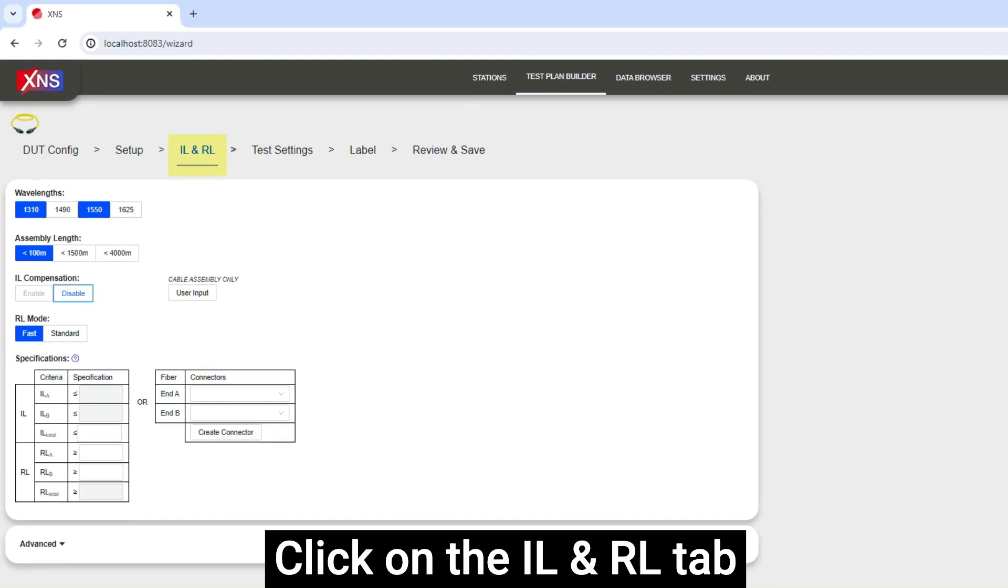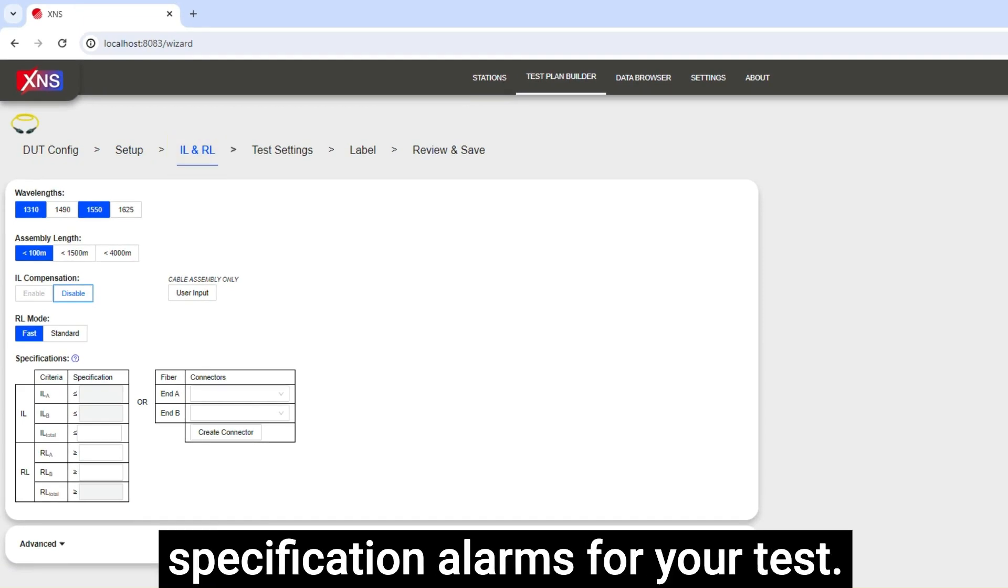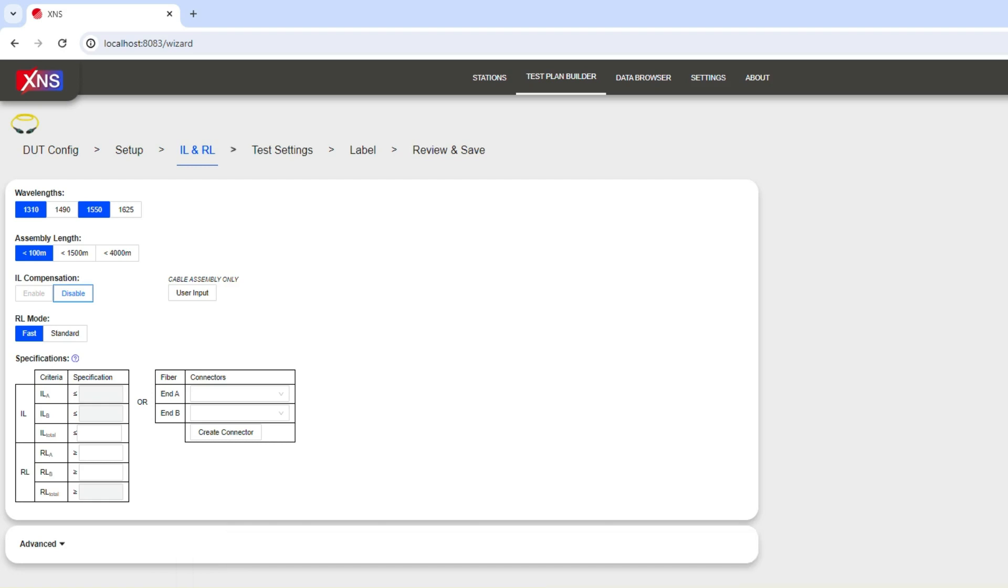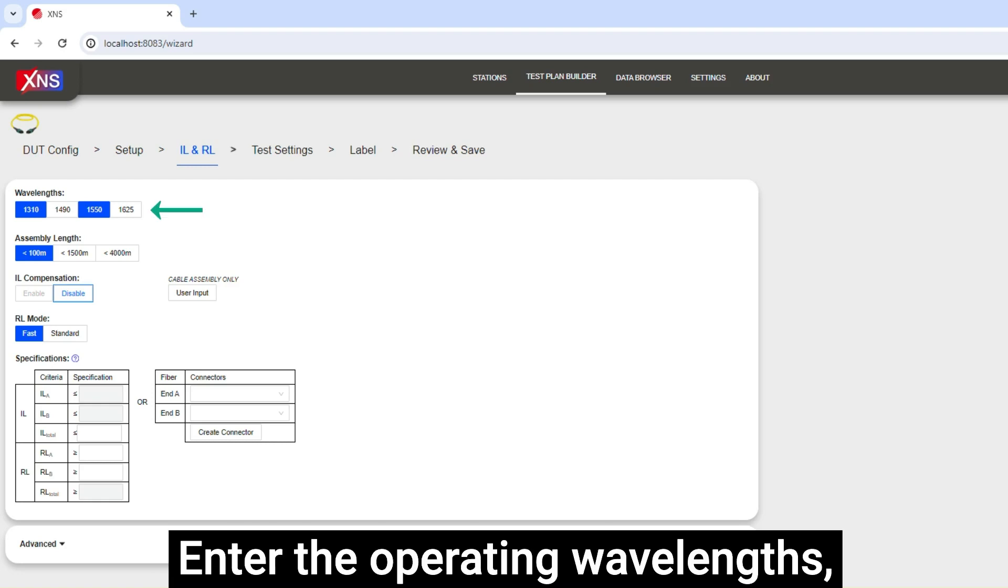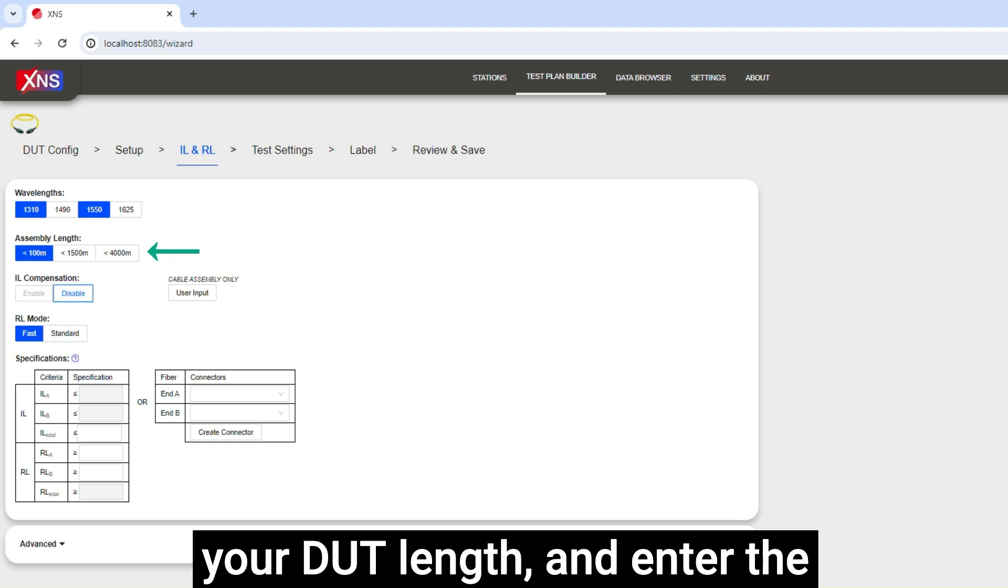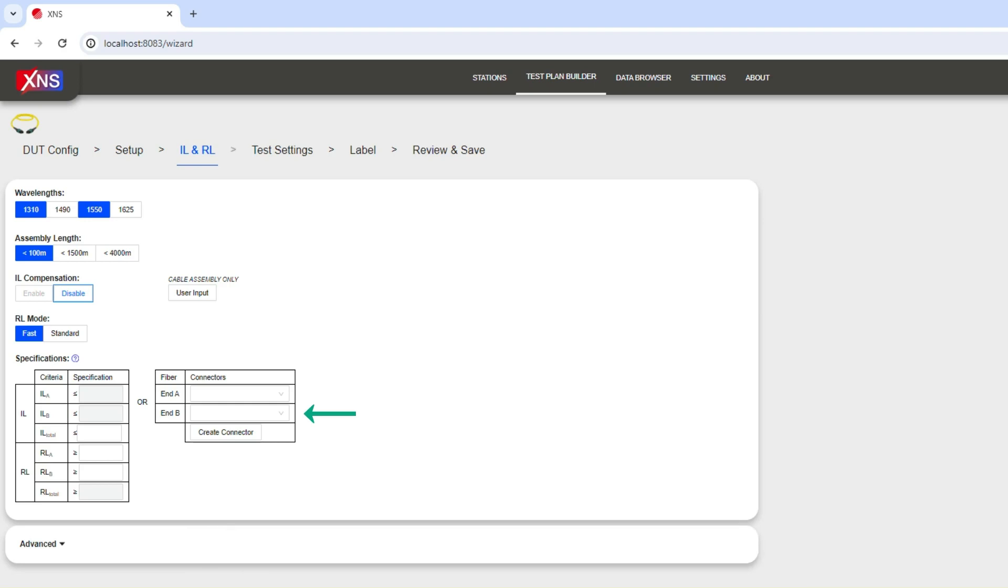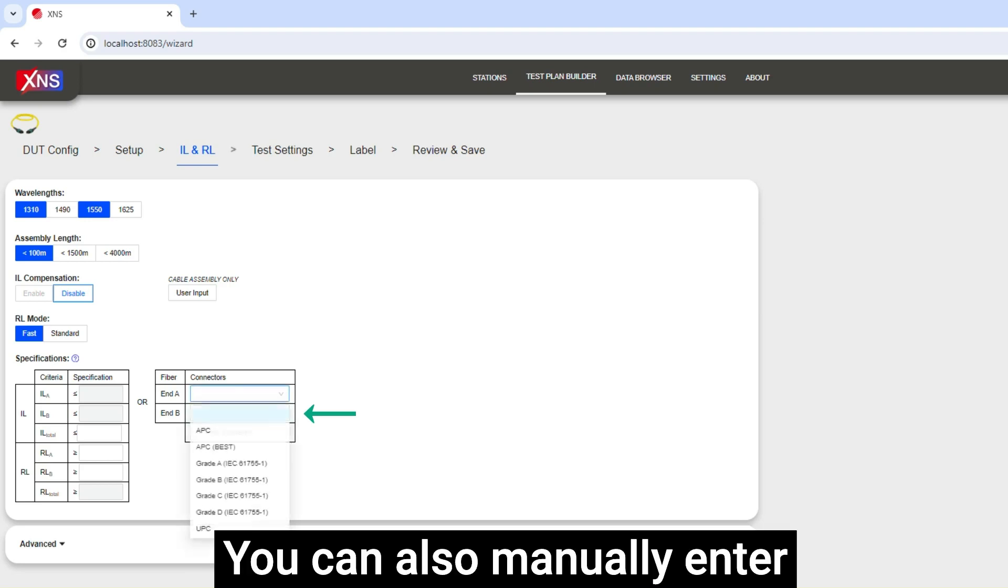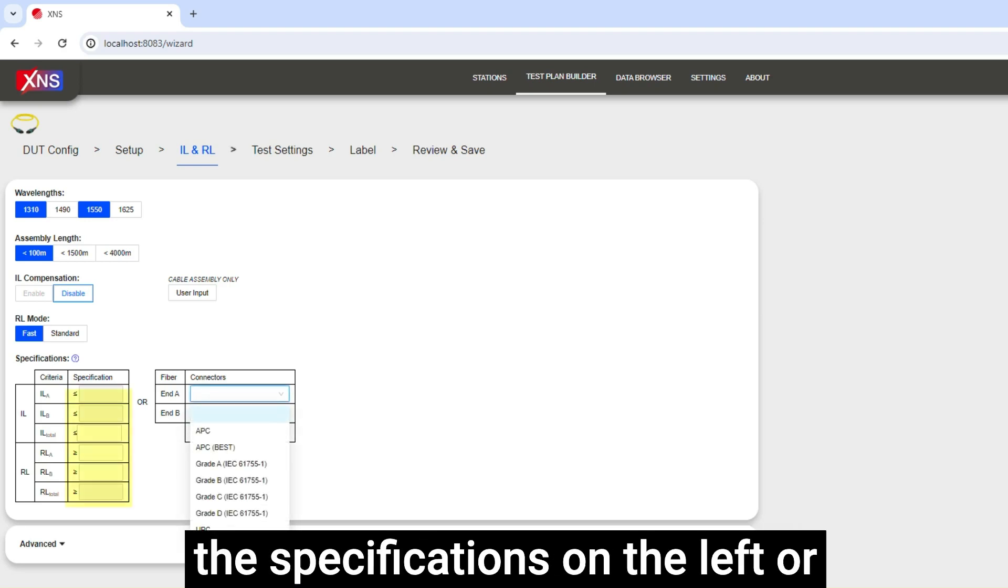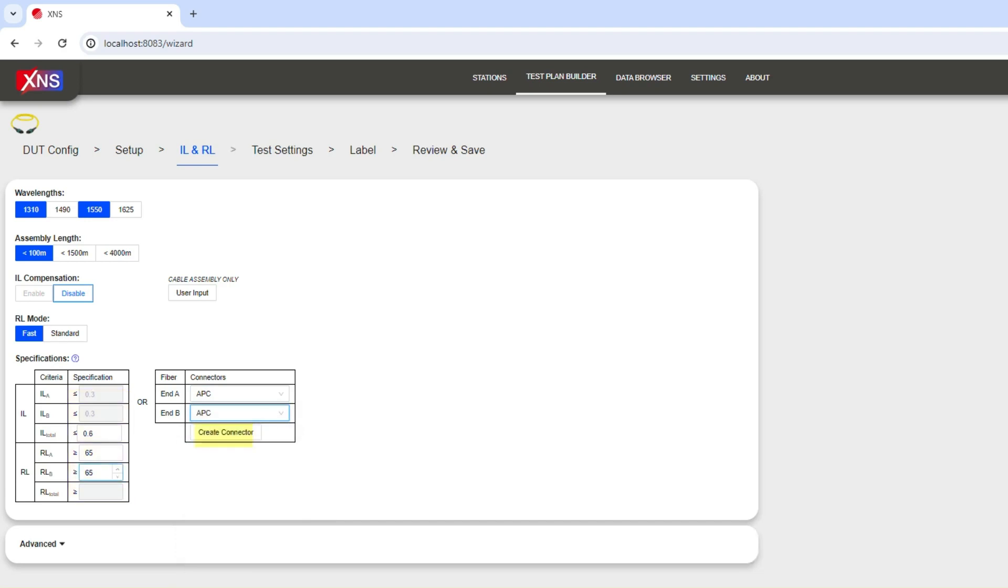Click on the IL and RL tab to continue and enter the specification alarms for your test. Enter the operating wavelengths, your DUT length, and enter the specifications for your cable. You can also manually enter the specifications on the left or pre-configure a new connector.